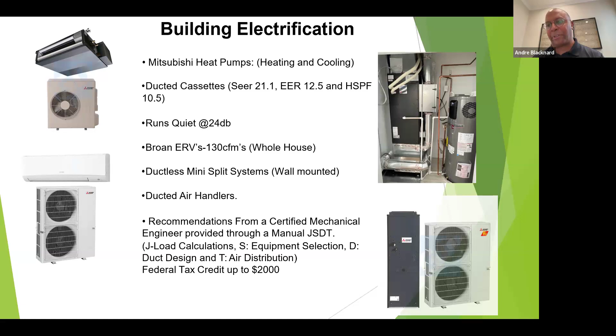When doing these buildings, we usually get these systems designed by a mechanical engineer, in a document called a manual J, S, D, T. J is for load calculations, S is for equipment selection, D is for duct design, and T is for air distribution. When inspectors do inspections on a house, they look for this document. It's stamped by an engineer, and it must be on site when you're getting inspected.